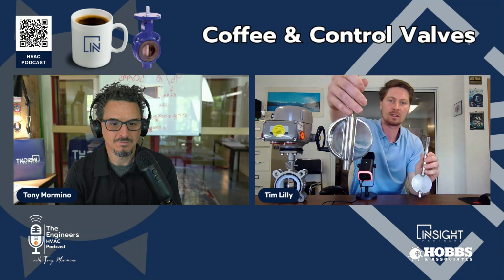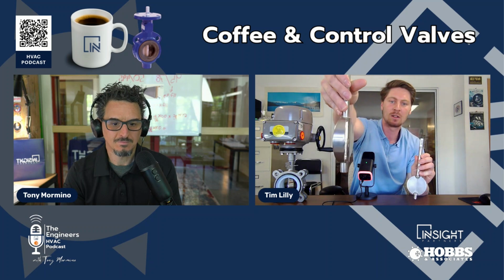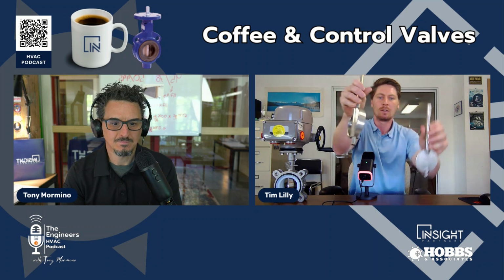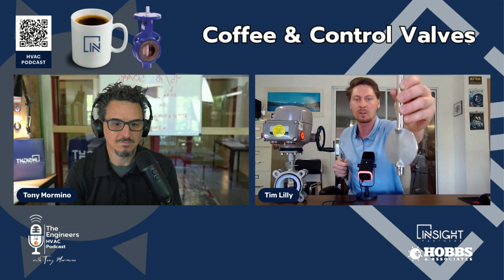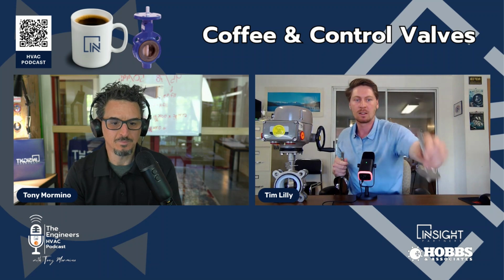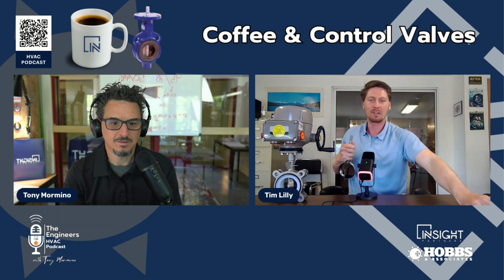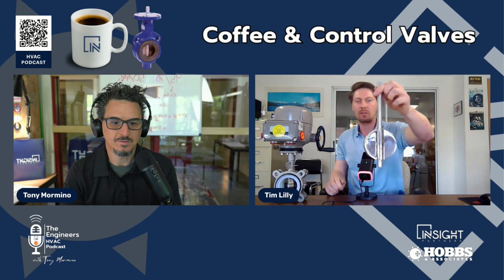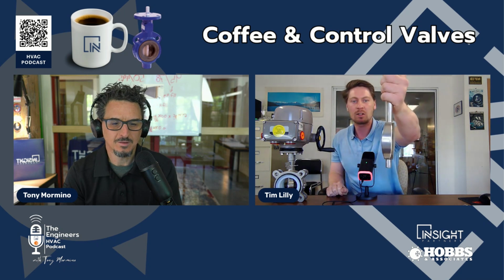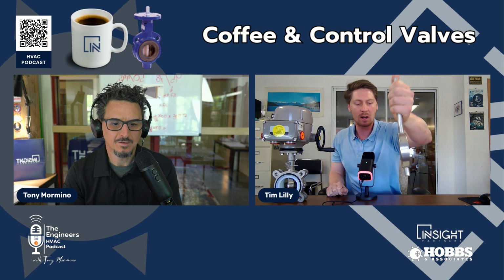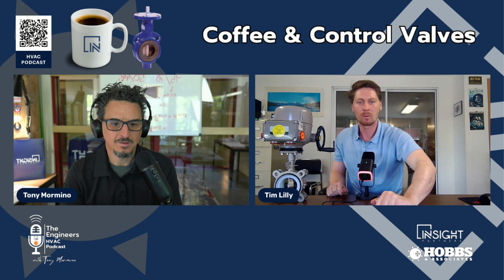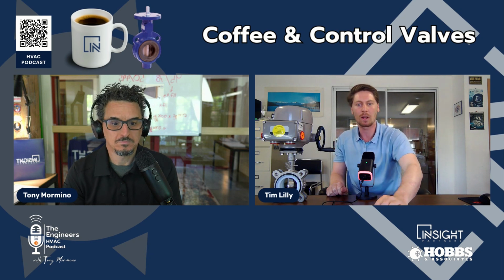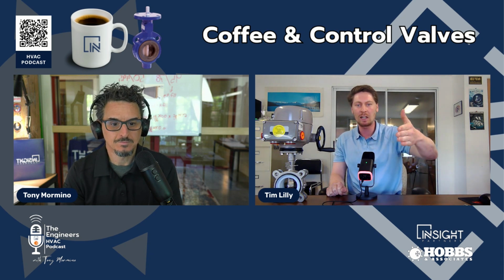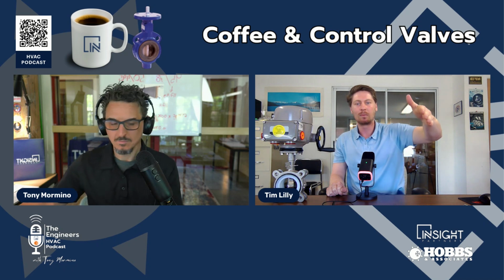So this is our disc. You can see we have recesses. We changed the geometry versus your standard butterfly valve disc, which is just a flat disc. It's just a plate. And so by changing the geometry of that disc, we can now teach a butterfly valve to operate along your equal percent flow curve, which gives you greater control over your set point. Let's say you're opening a chiller nice and slow and smooth and you want it to be on that curve.